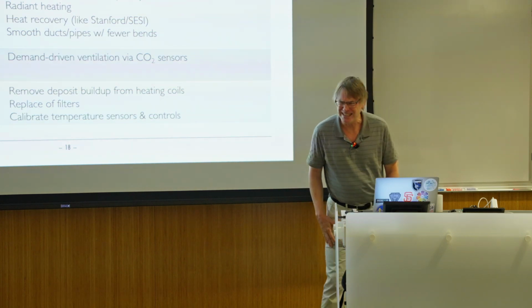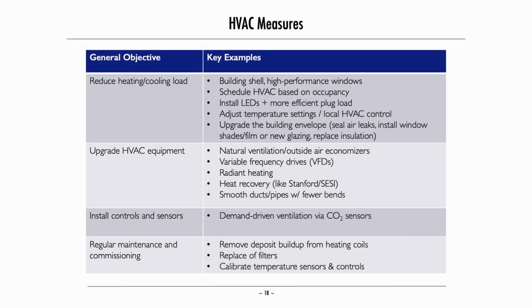So lighting's gotten pretty easy. Heating and cooling is still pretty hard—it's complicated, with a lot of steps to addressing heating and cooling loads. The first step, and the strategy they always recommend, is to start downstream and figure out how to reduce the load itself. What about that building shell? Can we add insulation, better windows, tighten the air leakage, those sorts of things? Can we reduce heat loads from equipment like lighting with more efficient lighting? All of those things reduce the load on the heating and cooling system.